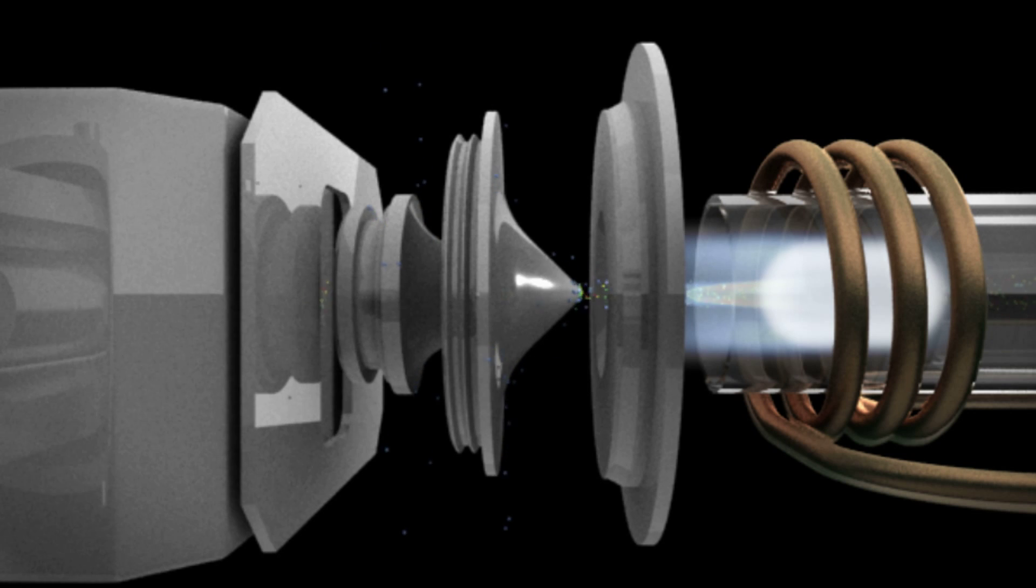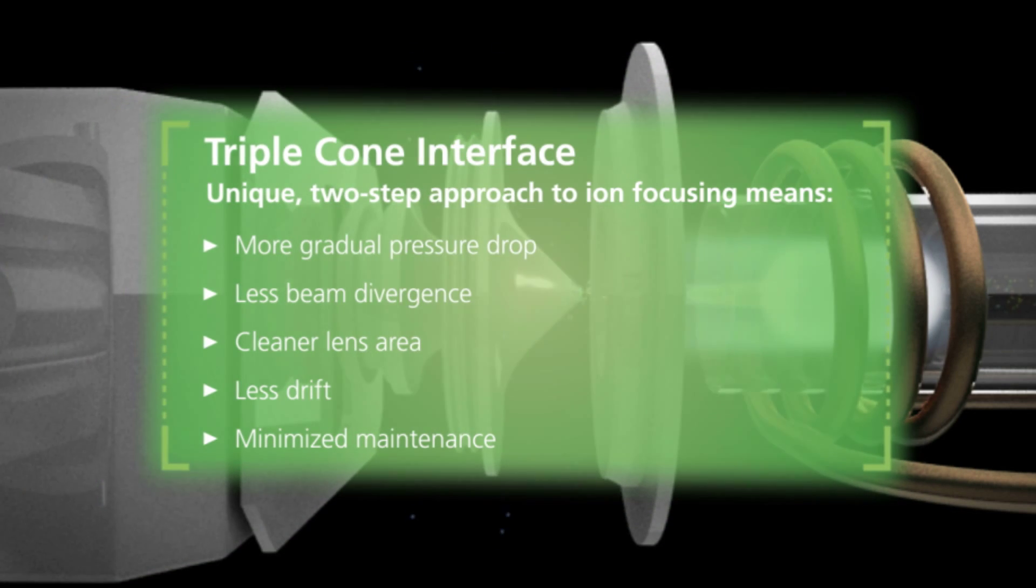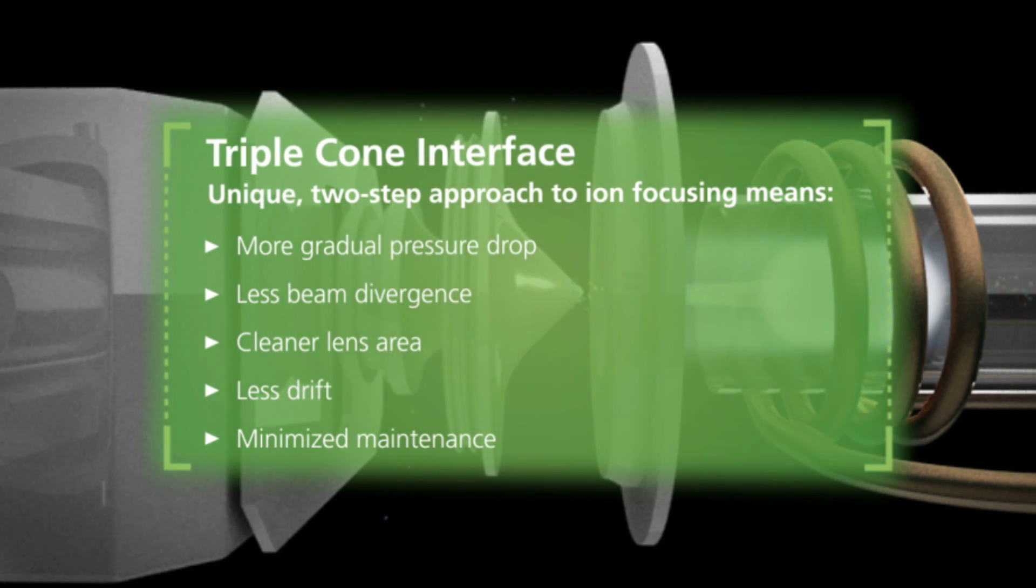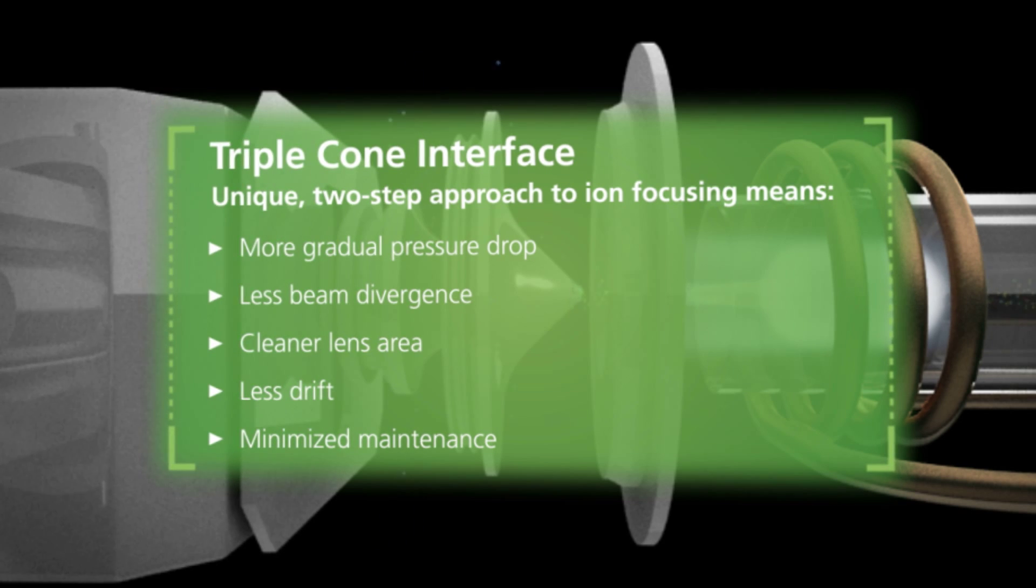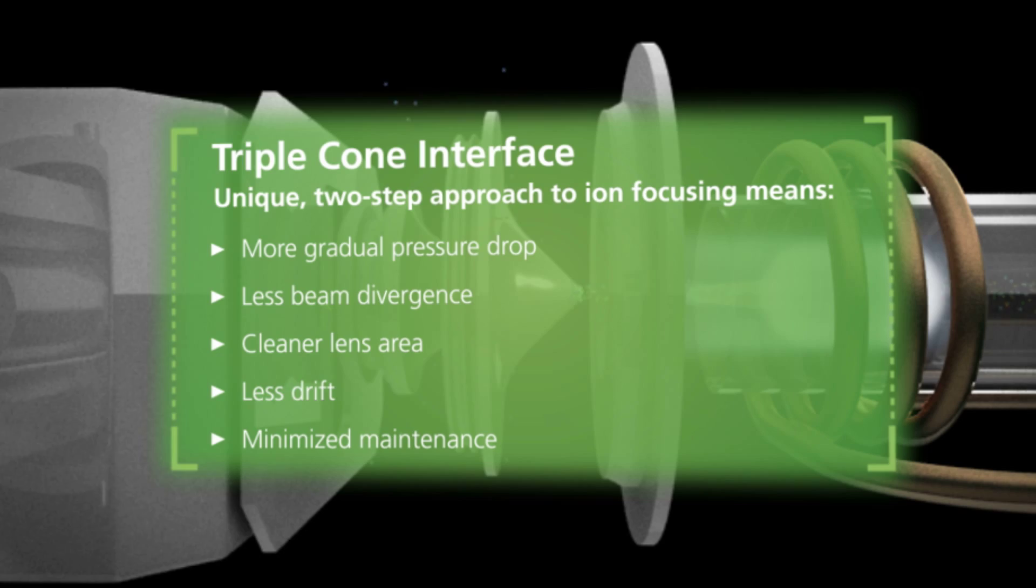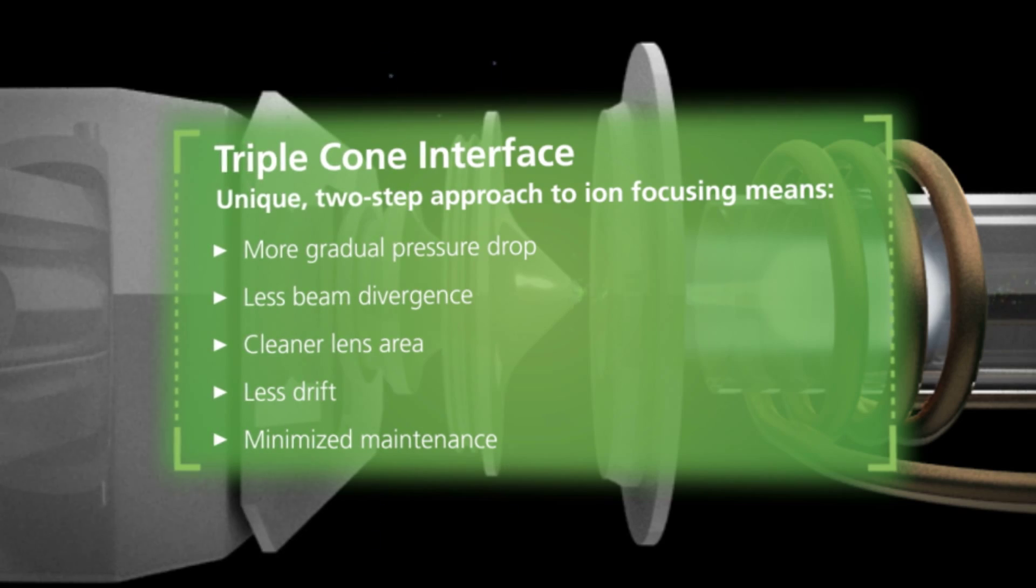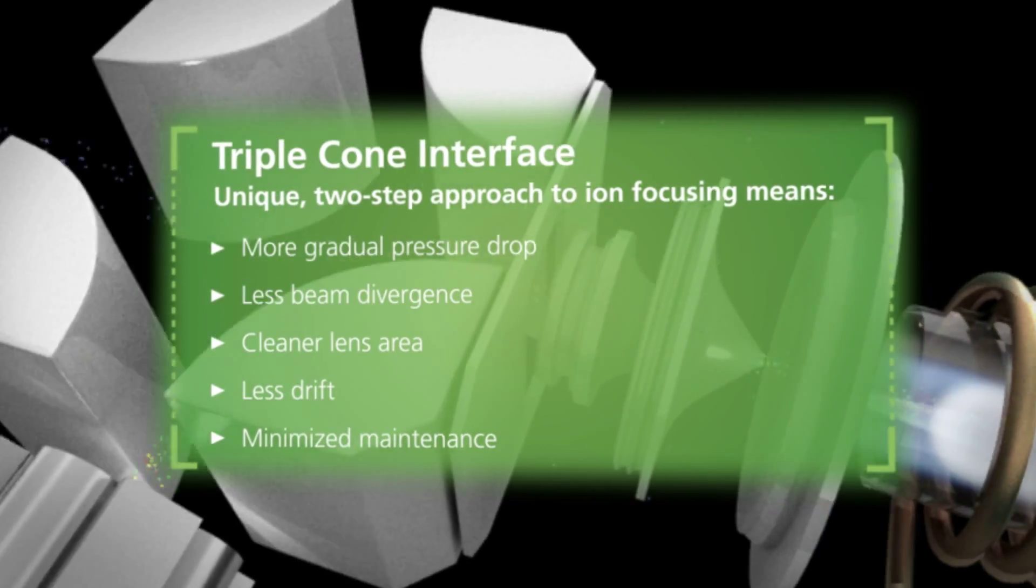The only one of its kind, this triple cone design offers an unprecedented level of beam focusing by removing the greatest quantity of unionized material, keeping the inside of the mass spectrometer clean and giving the instrument an unsurpassed level of stability.